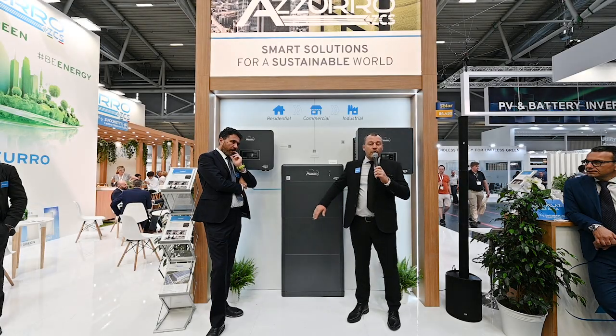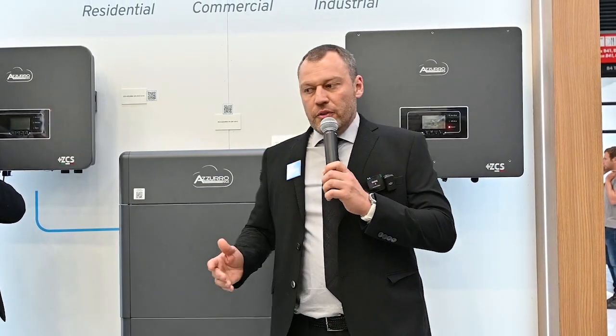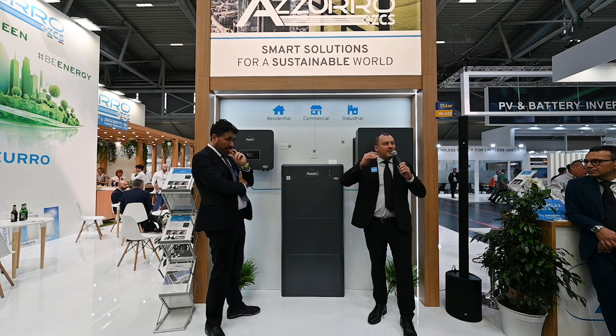The main difference between these systems and the other one is related to the battery system. The battery tower we saw on the other side is composed of modules in series, self-balanced through direct connection. This battery concept is slightly different because it has an integrated DC-to-DC converter, making it a 400-volt high-voltage battery. The connection is therefore parallel, not series, allowing the customer to install, add, or remove each single battery whenever they want without worrying about balancing.